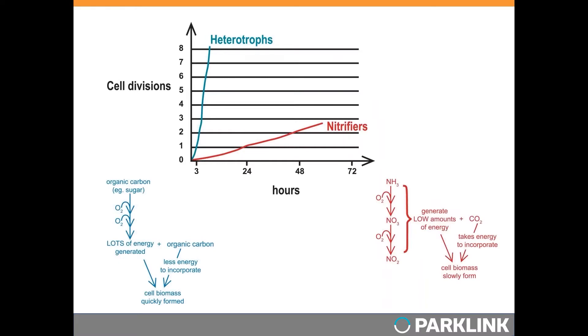To illustrate growth rates based on wastewater at 70°F: the doubling time for heterotrophs could be anywhere from 20 to 40 minutes or even less, whereas the doubling time for nitrifiers is anywhere from 24 to 48 hours — and in some cases longer. Nitrifiers build faster in warmer water and slower in cooler water.